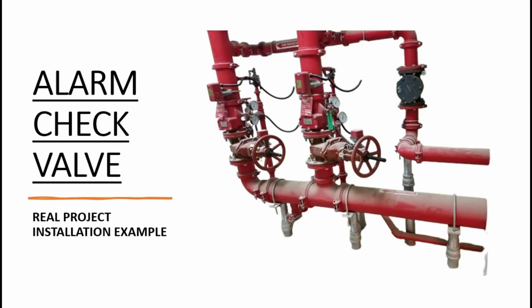Now let us see one real life project example. This photo is to show you how the alarm check valve is actually installed. So you can see this is the main supply line. This one will be 4-inch or 6-inch, and then it goes to two zones. So maybe this riser goes to zone 1, and this goes to zone 2. If you have 3 zones, then we need 3 risers. If you have 4 zones, then we need 4 risers.